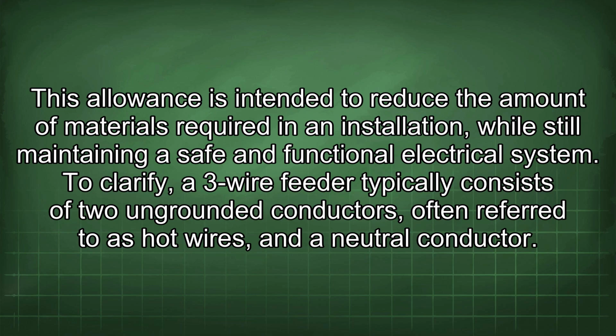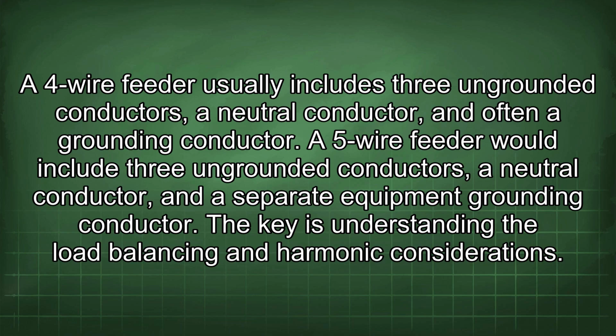To clarify, a 3-wire feeder typically consists of 2 ungrounded conductors, often referred to as hot wires, and a neutral conductor. A 4-wire feeder usually includes 3 ungrounded conductors, a neutral conductor, and often a grounding conductor. A 5-wire feeder would include 3 ungrounded conductors, a neutral conductor, and a separate equipment grounding conductor.